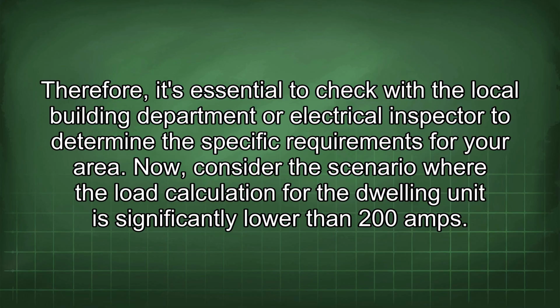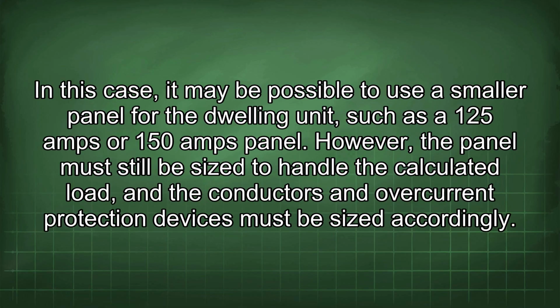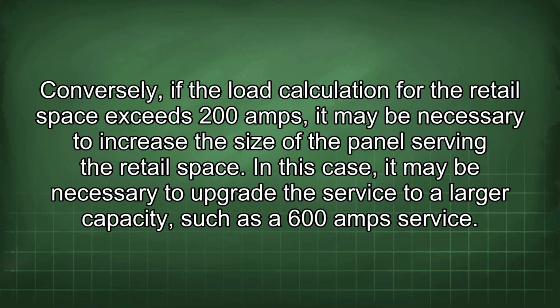Now, consider the scenario where the load calculation for the dwelling unit is significantly lower than 200 amps. In this case, it may be possible to use a smaller panel for the dwelling unit, such as a 125 amps or 150 amps panel. However, the panel must still be sized to handle the calculated load, and the conductors and overcurrent protection devices must be sized accordingly. Conversely, if the load calculation for the retail space exceeds 200 amps, it may be necessary to increase the size of the panel serving the retail space.